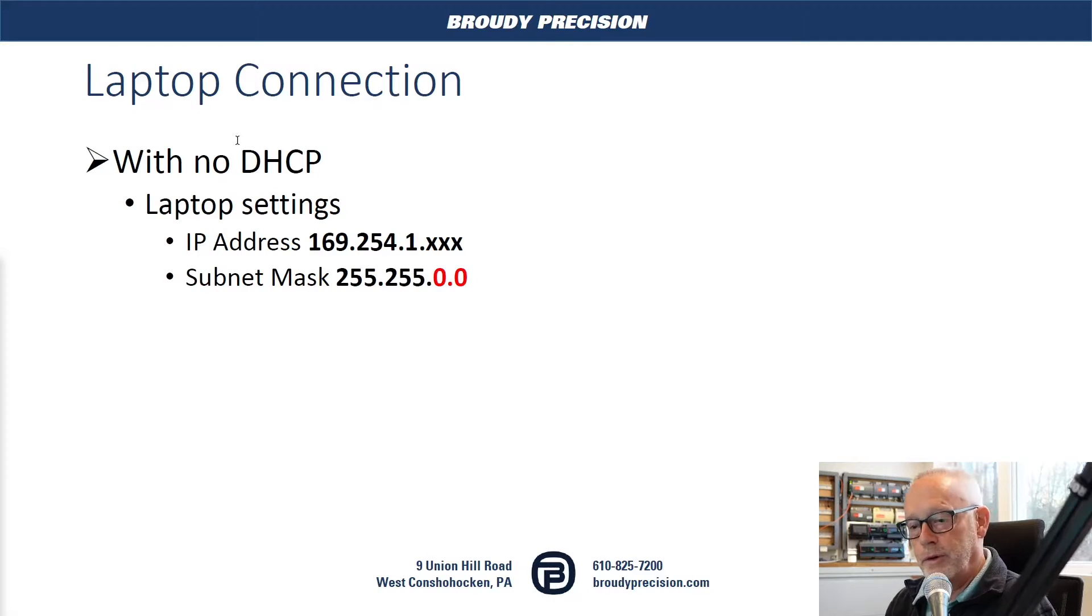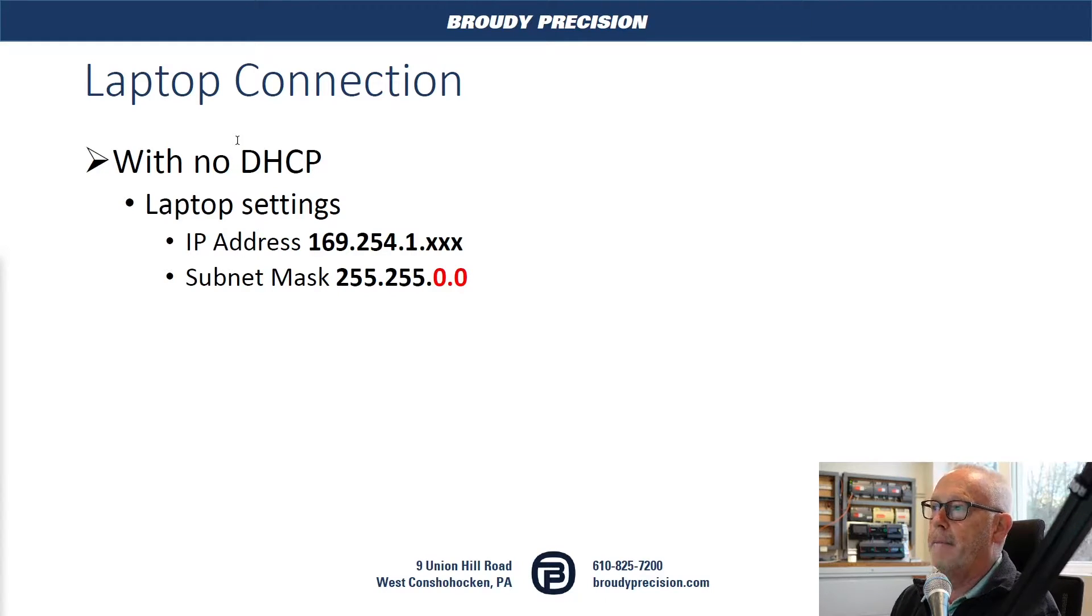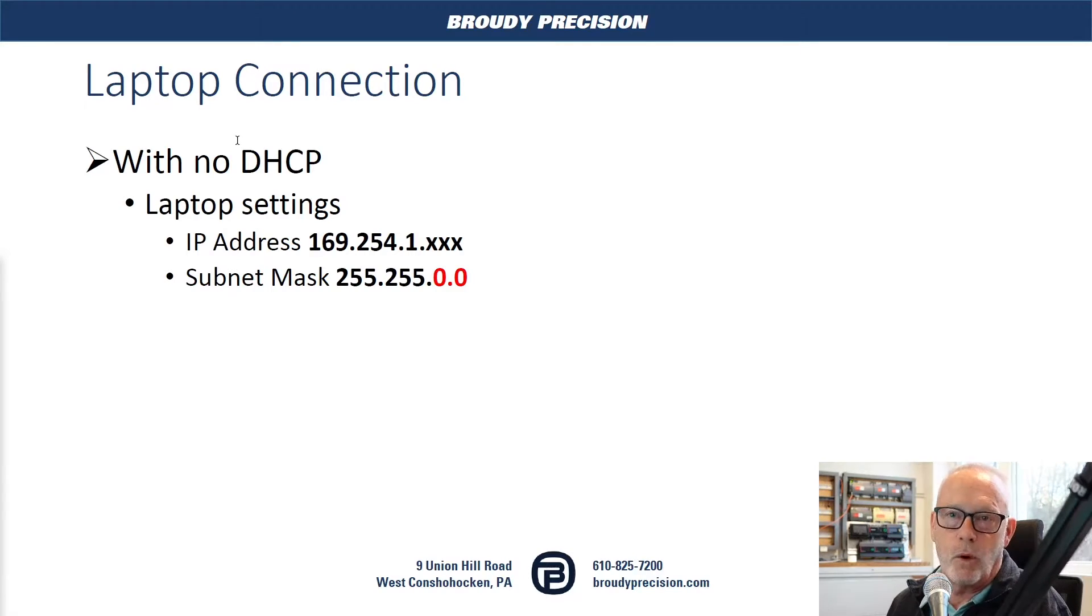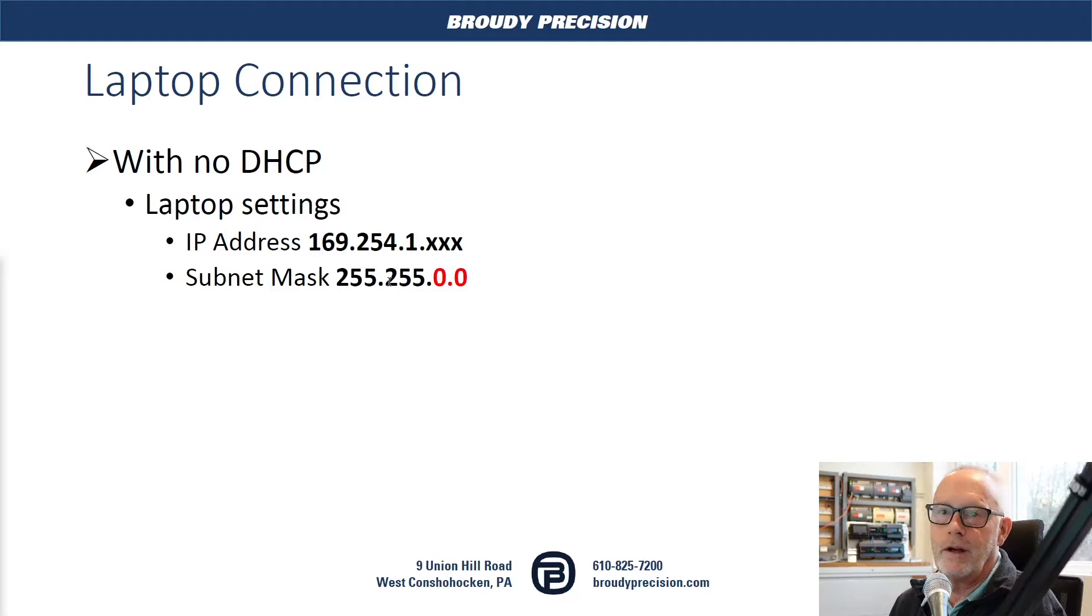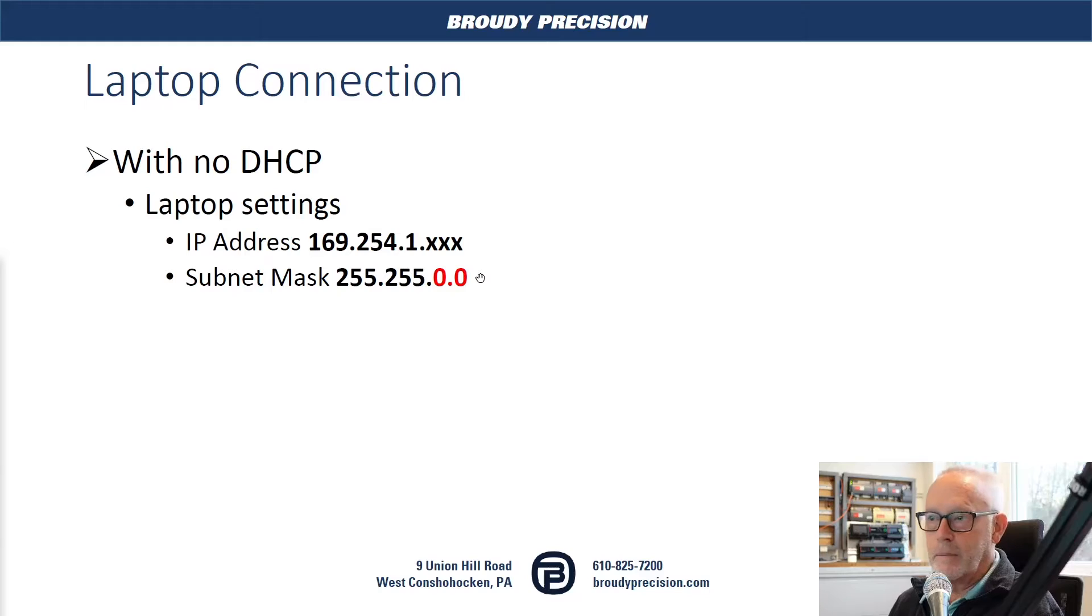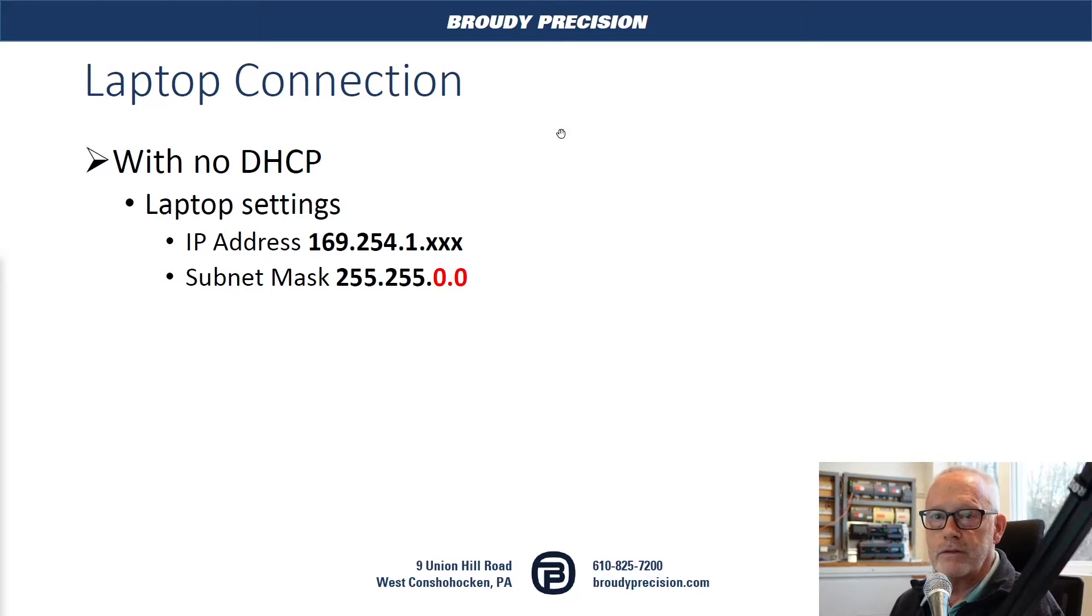And then for your computer to be able to talk to the controllers if you don't have DHCP, you have to make sure you set up your IP settings correctly. So because you're on that subnet 169.254.1 on the controllers, you obviously need to set up your PC the same way. One big change or one big thing to look for and to make sure you do is set the subnet mask for 255.255.0.0. If you set it for three 255s and then a .0, you're not going to find your controllers. I have found that when you have it set that way, you can ping it, you can go in there, type in the IP address. It will respond, no problem at all. But BACnet will not recognize the controllers addressing. So as long as your computer is set up for 255.255.0.0, you should be able to communicate just fine.